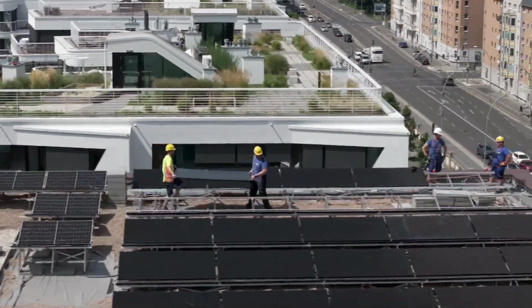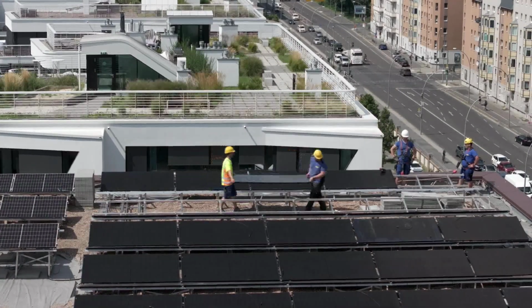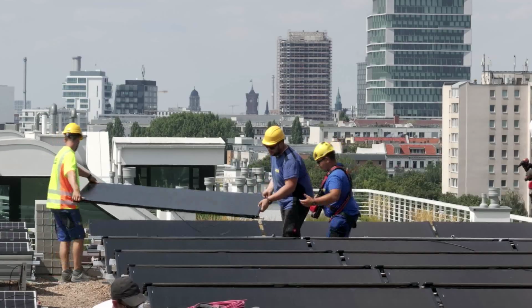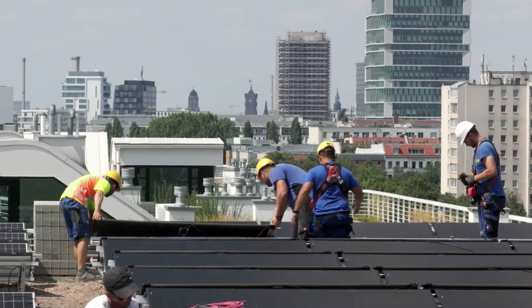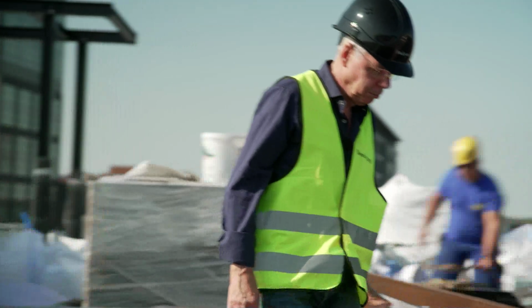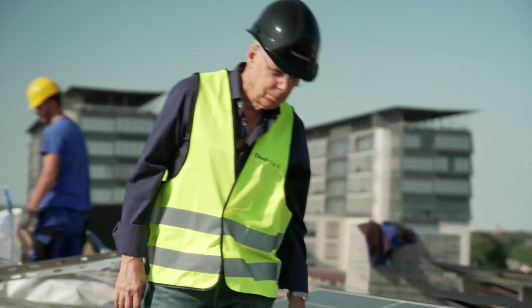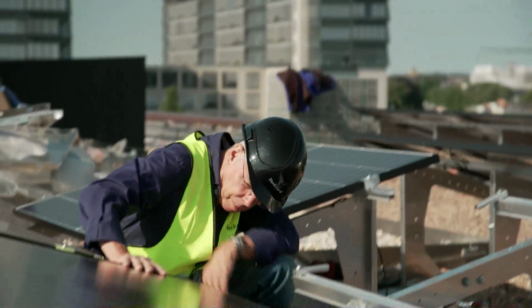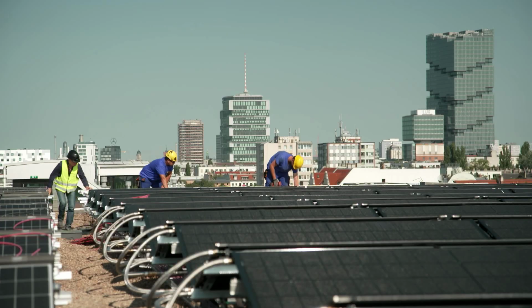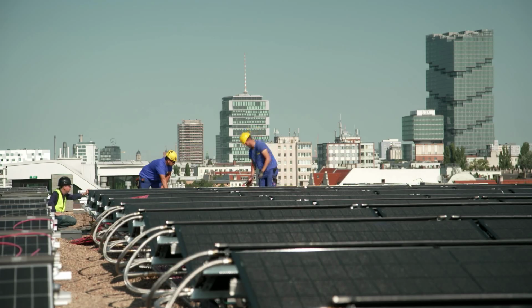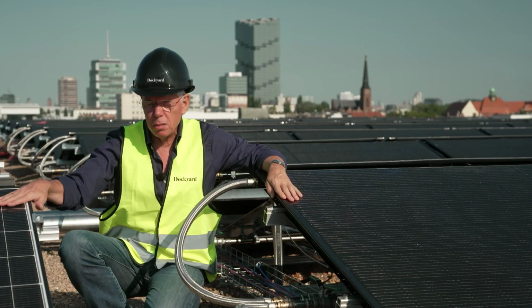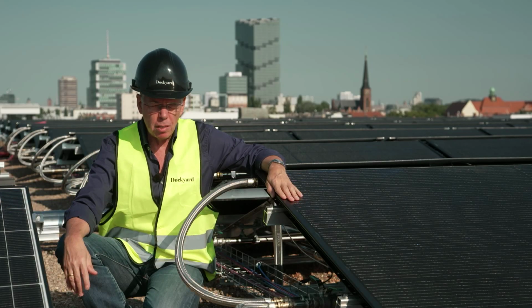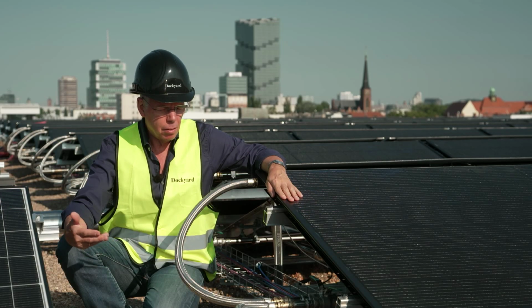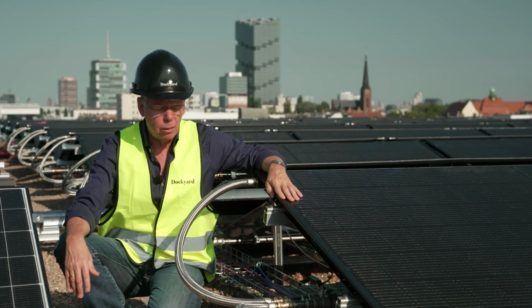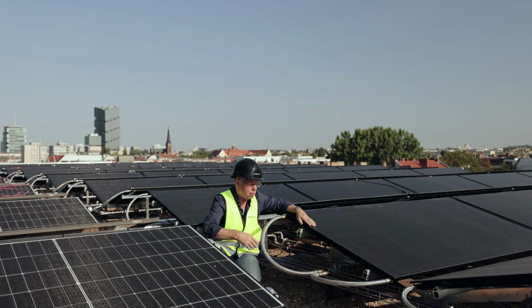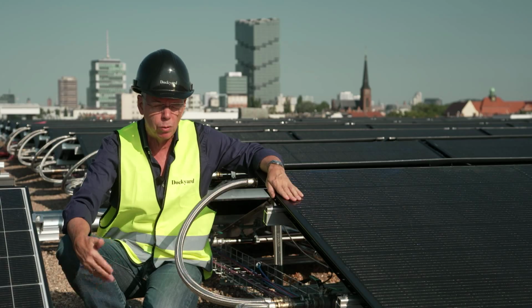In order to have sufficient ambient heat available, technicians install a supplementary energy source on the roof of the building. In addition to a conventional photovoltaic system, they also use a special kind of solar module. Michael Viernickel helped develop the building's complex energy management system. Solar energy provides us with radiation that we can use to create electricity, like in the collectors here on the right. However, we are only able to obtain around 20% of the energy. But there is a large amount of heat that also comes from the sun, and if we want to utilize this heat, we use photovoltaic thermal hybrid solar collectors, or PVT collectors.